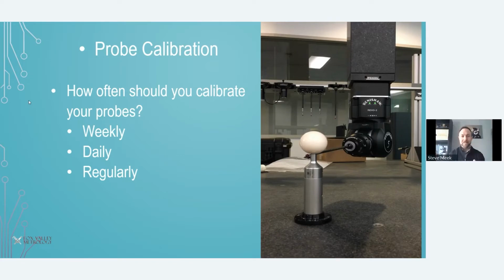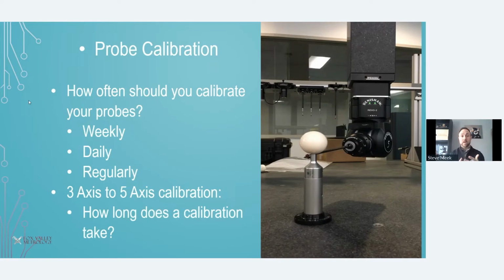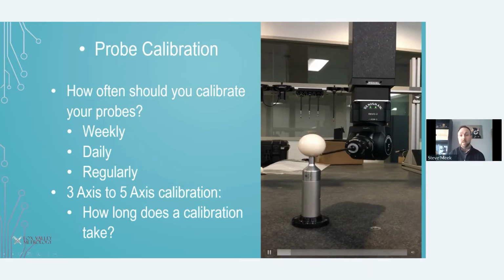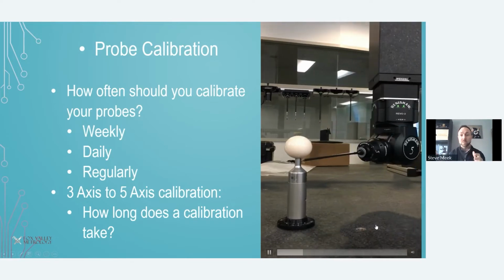How long does a 5-axis calibration take compared to a 3-axis calibration? Somewhat of a loaded question because it depends on a lot—how many different tips and angles are built into your probing configuration, your machine approach and retract speeds, these types of things come into play. But in general, you can calibrate a 5-axis PH20 or a Revo in about half the time you can a 3-axis PH10 or similar.